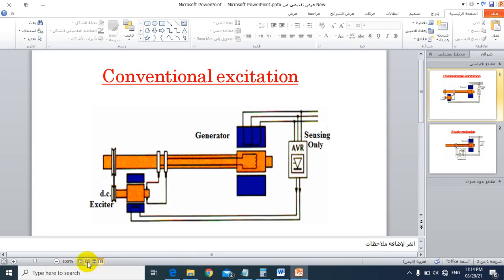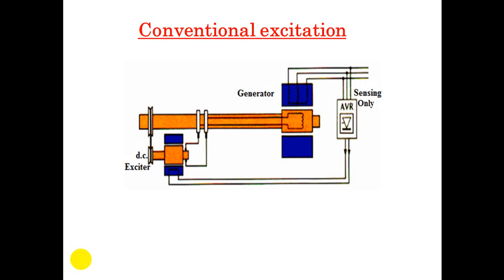In the last lessons, we explained the construction of the three-phase synchronous AC generators. Today, we will explain or talk about the synchronous generator's excitation. The exciter is the backbone of the generator control system. It's the power source that supplies the DC magnetizing current to the field winding of synchronous generators, thereby ultimately inducing AC voltage and current in the generator armatures.